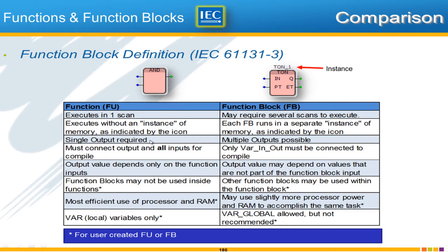Another property of a function is the single output. Every function will have just one output, while a function block may have one or more. You must also connect all outputs and all inputs for a function to compile — you can't leave any disconnected. This is not the case with a function block; the code will compile if you don't connect outputs or certain inputs, though some inputs may be required. You won't get a successful build with a function if you don't connect all inputs and the output.